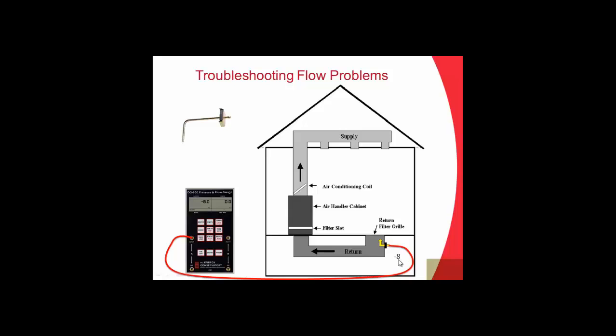So what are we measuring? I put the DG700 outside the house here so I could make it a little bigger, but actually when we're taking this measurement, we're going to be standing in the house. So we're measuring the pressure in the duct with respect to the main body of the house. We're measuring the pressure across this return air grill. So if you're measuring this from the crawl space, you'll need to run another tube up into the room. So we're measuring the room, and the pressure across this return air grill.